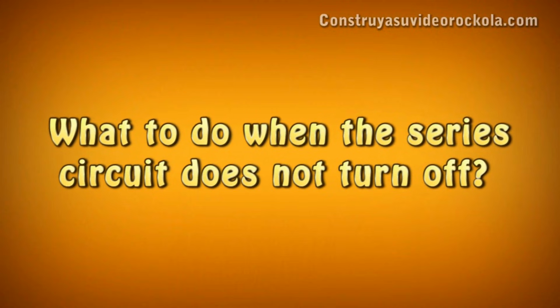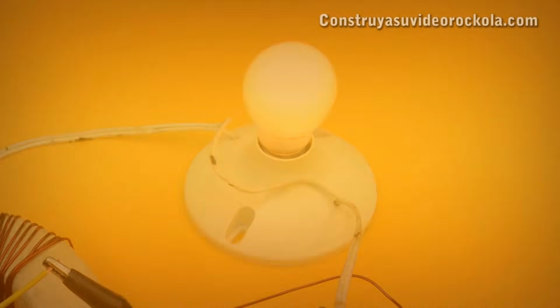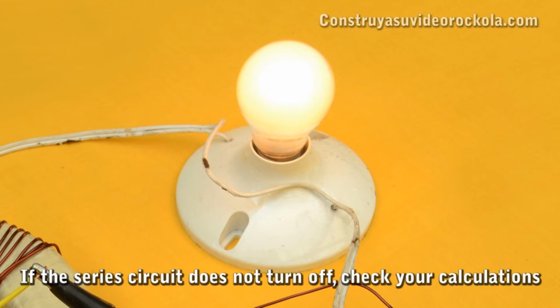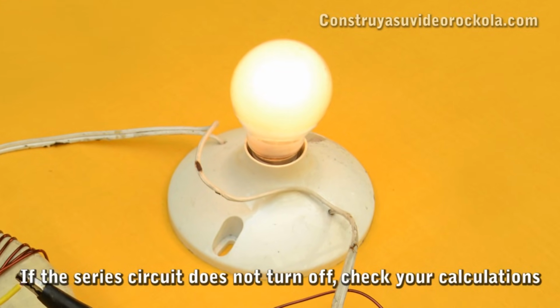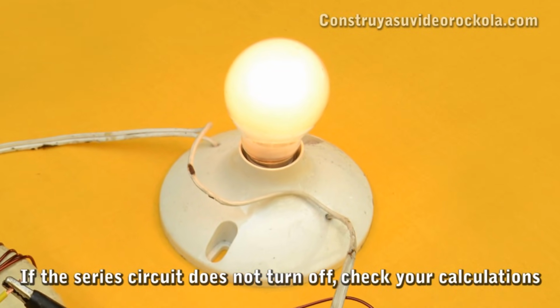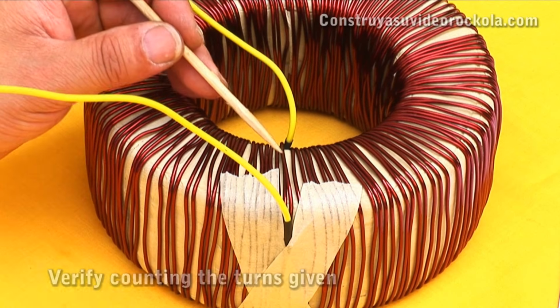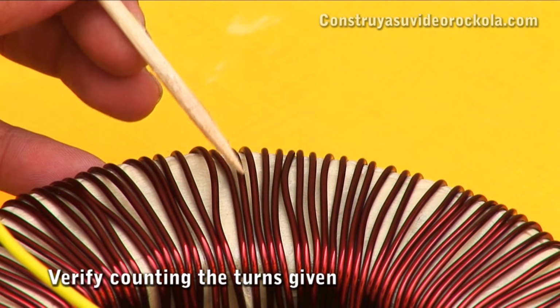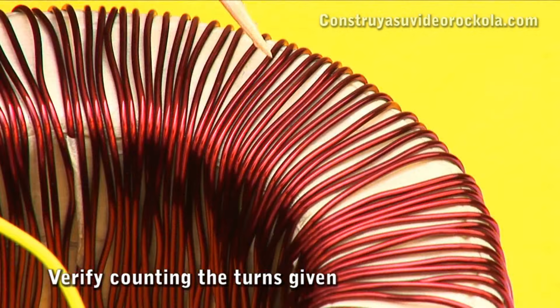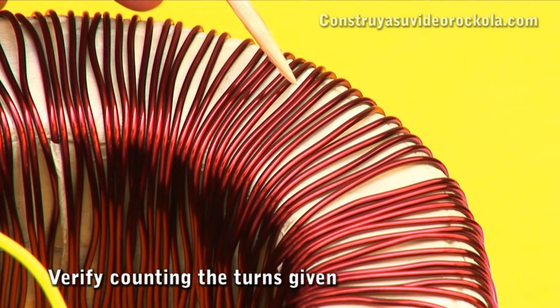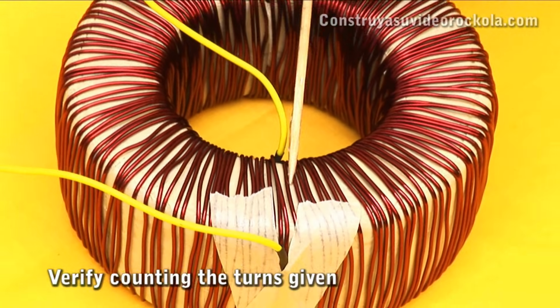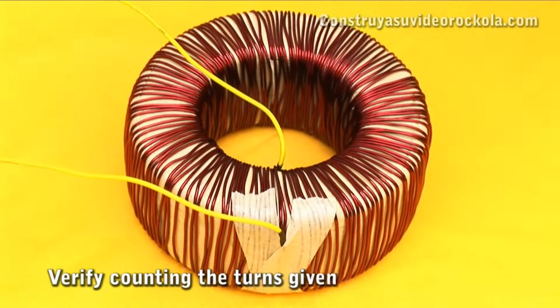What to do when the series circuit doesn't turn off? When the series circuit doesn't turn off, it indicates a lack of turns of wire, that the calculations were wrong, or that the core is of bad quality. We must continue winding wire until the series circuit turns off completely. Now that the series circuit turns off, we count all the turns of wire, obtaining a total of 144 turns.